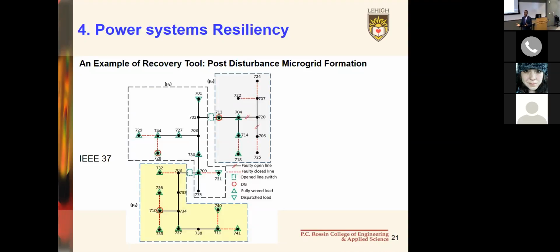Otherwise, because that was not the only substation you had in the system, the other ones failed, you only have that one remaining. If you have to feed the entire area with that substation, you won't be able to do it. So you have to open some lines and pick up just as much as you can so that they still have energy. But that's really not the architecture from transmission to sub-transmission, substation, which usually flows downward.